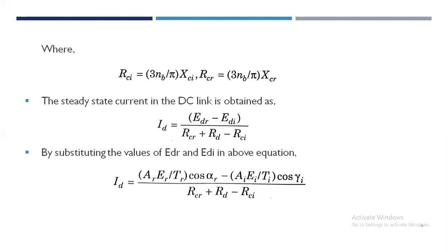The currents during line faults are automatically limited with the rectifier station in current control. But there is a need to maintain a minimum extinction angle at the inverter to avoid commutation failure. It is economical to operate the inverter at constant extinction angle, that is CEA, which is slightly above the absolute minimum required for the commutation margin. This results in reduced cost of the inverter station, reduced converter losses, and reduced reactive power consumption.